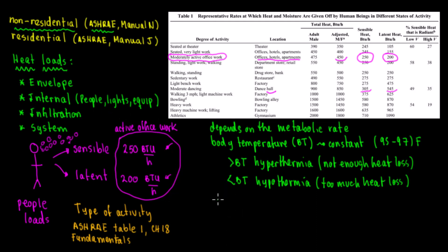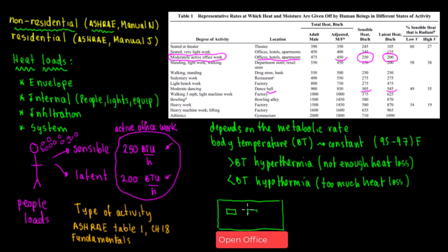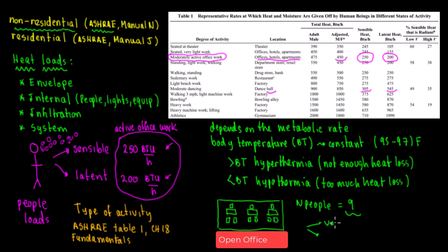People load is very important in practice. For example, in a large open office, the architect provides drawings and will show you the chairs. You count the number of chairs — say nine chairs means nine people. That number is important for two things: calculating the ventilation and calculating the people heat load.